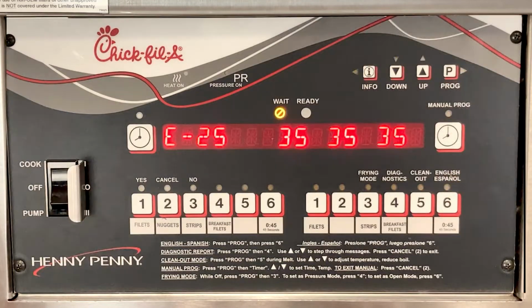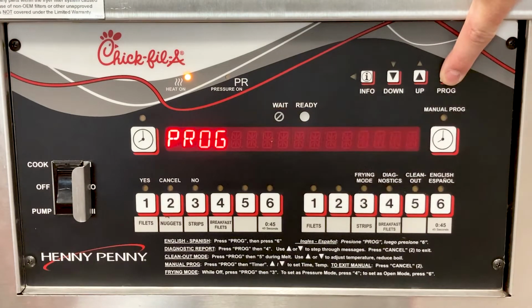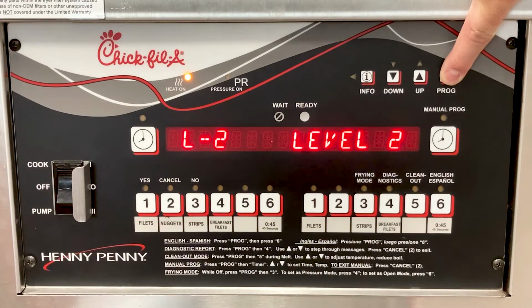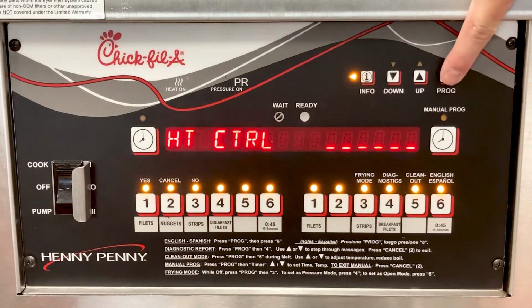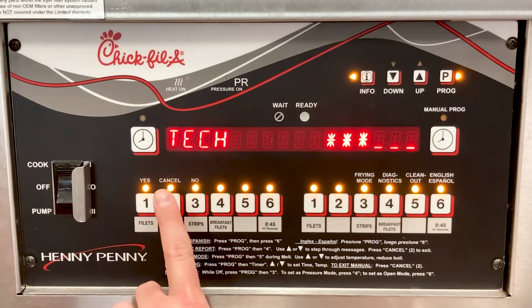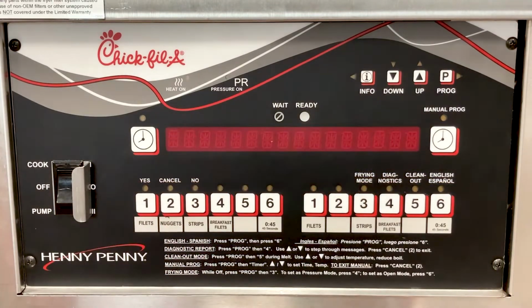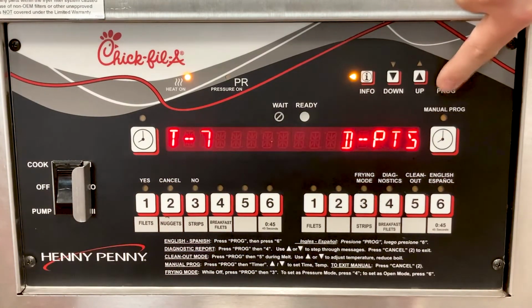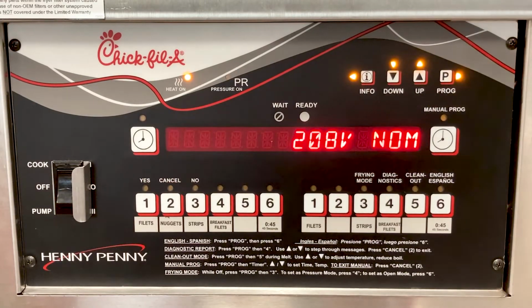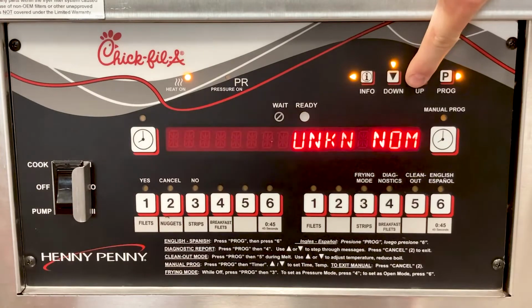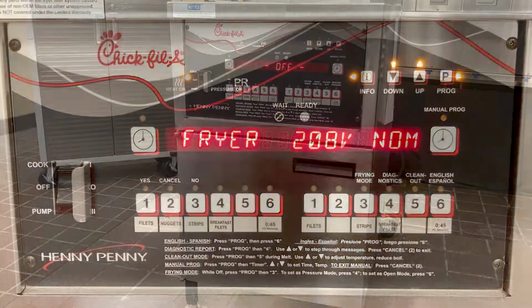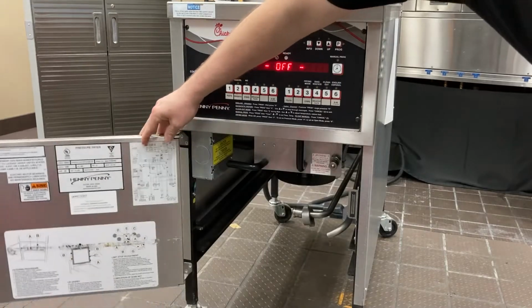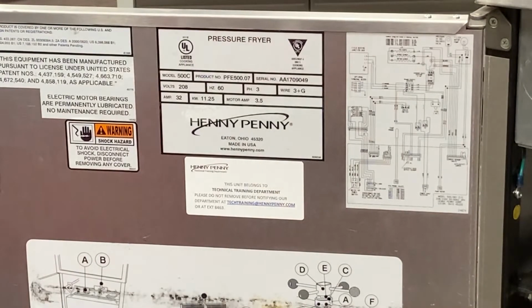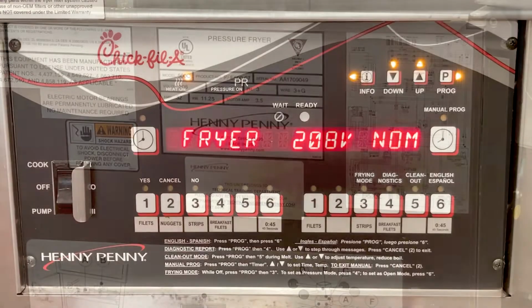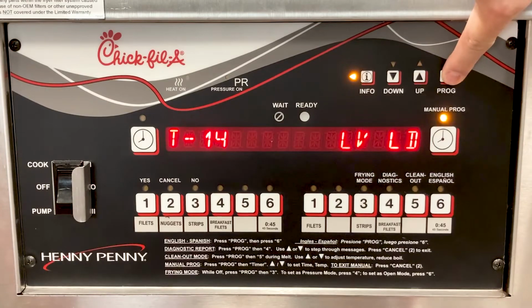If the unit is displaying all three amp readings with the same number and look to be normal, enter tech mode by pressing and holding the P button until level 2 programming comes up, and then use the P button to scroll over to tech mode and enter the code 11221122. Once in tech mode, use the P button to scroll over to T13 and make sure the nominal voltage is set correctly. Use the up and down arrow keys to change the nominal voltage setting, making sure that it matches the data plate on the inside of the door. If this is not correct, it can give the error code with no components broken. Press and hold the P button to exit tech mode.